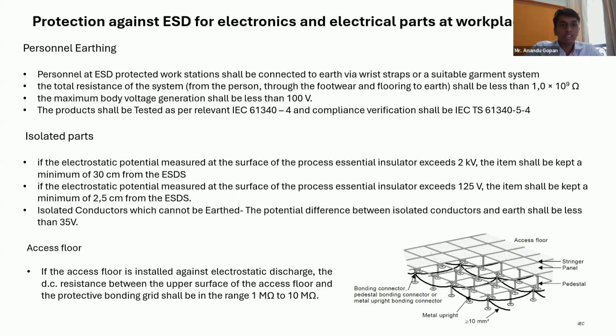There are some footwear or ESD-protected wrist straps, which will be connected to your protective earth or equipotential bonding point. At the end of the day, all of this system together must have a resistance less than 10 to the power 9 ohms.